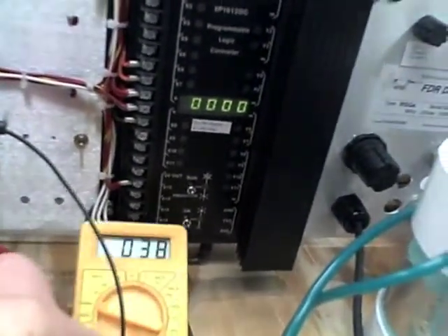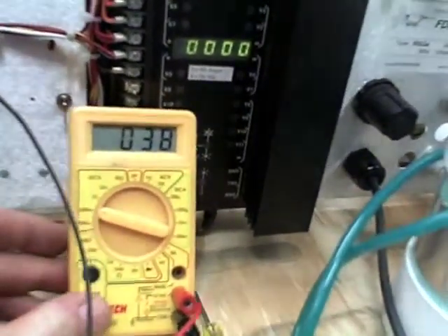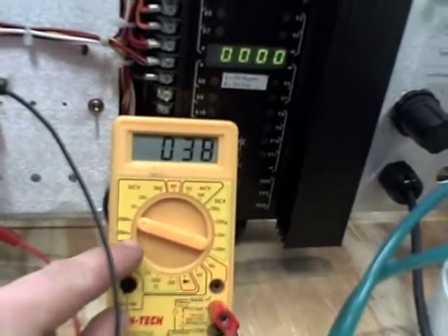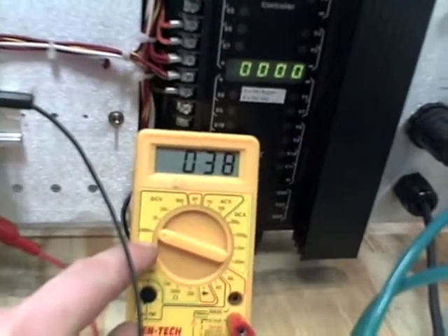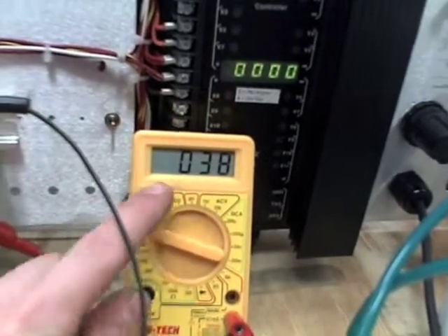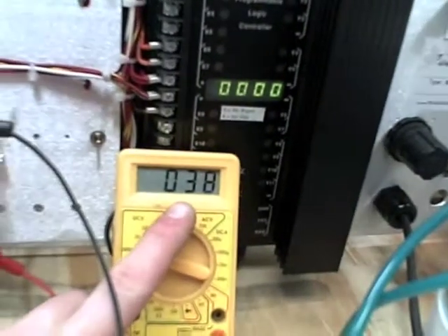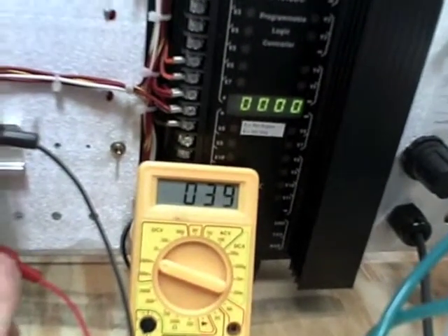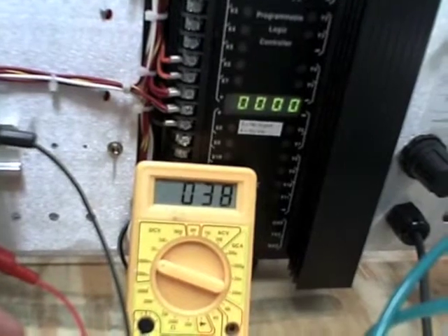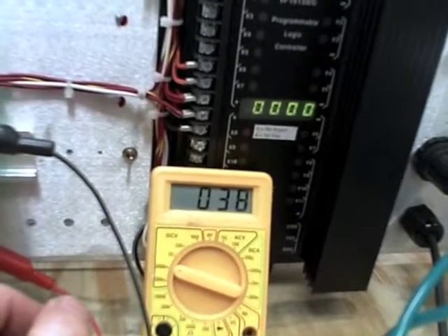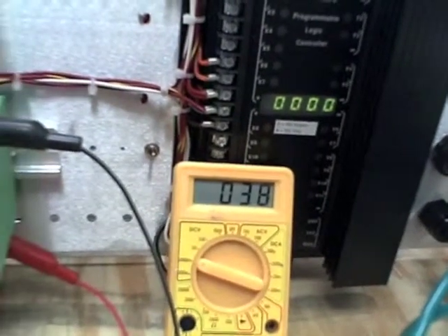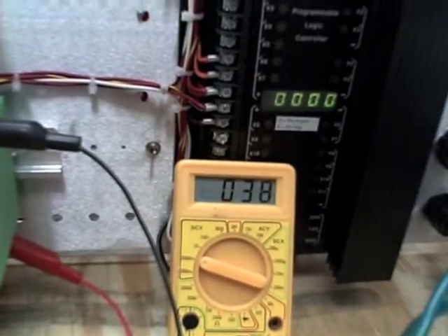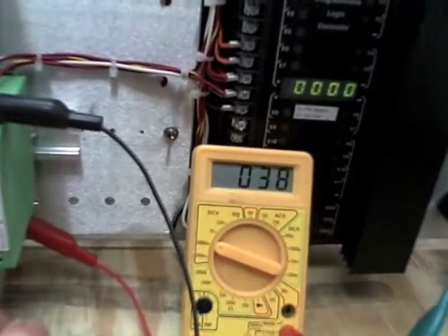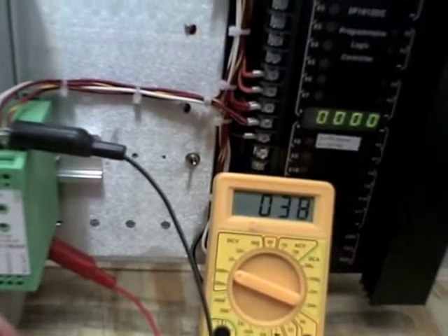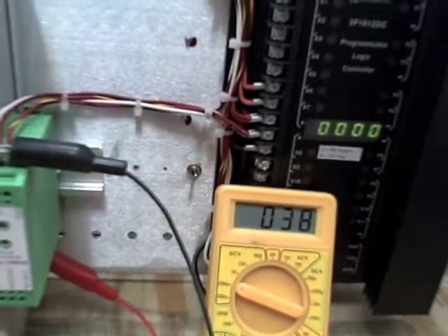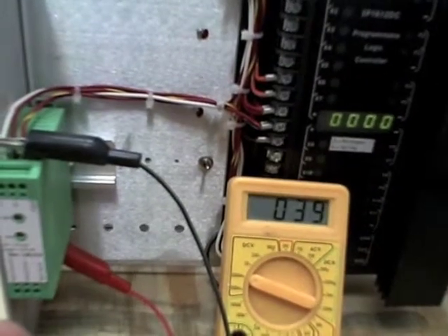I want to turn on my voltmeter and set it to 2000 M on DC volts, and what that's going to do is display millivolts now. So now I'm looking at 38 millivolts is what it's reading. And as we go through the calibration, you'll see this number change, but for the first part, the first adjustment, we're going to want to set this right around 13 millivolts, and you can be plus or minus a little bit there too. The big thing is that it's a steady number and it settles down, it's not jumping around.